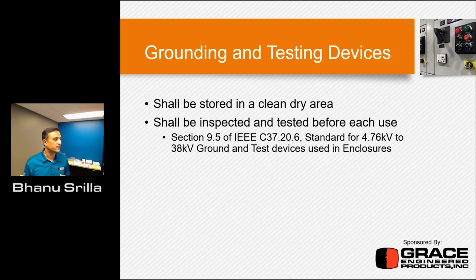So grounding and testing devices is another area, which shall be stored in a clean and dry area, and also shall be inspected and tested before each and every use. So this is the one thing, it's not like once in a year or once in 3 years. You have to test this and inspect this before each and every use. And if you want to look at what those guidelines are, it's defined in IEEE C37.20.6, which is the standard for 4.76 kV to 38 kV ground and test devices used in enclosures.